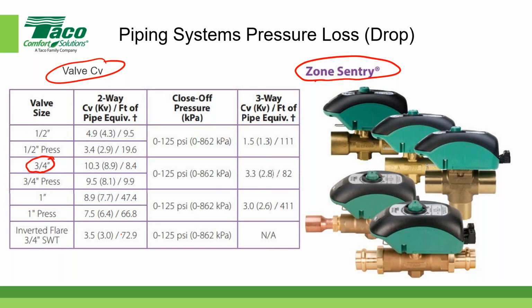What that means is that this valve will allow 10.3 gallons per minute to pass through the valve at a pressure drop of 1 PSI, all right? And if you remember from that previous slide, if I multiply the CV by 0.86, yeah, 10.3 times 0.86 comes out to approximately 8.9. And there's that KV value that we put in parentheses. And it has the equivalent length of 8.4 feet.